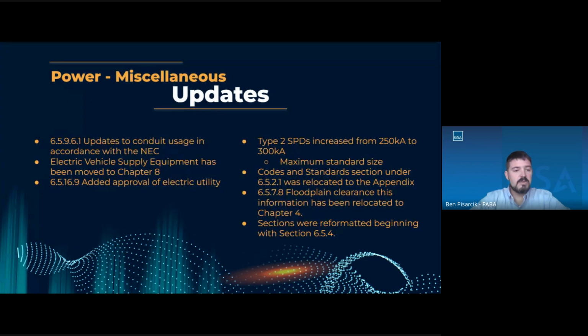Okay, moving on with general updates. So we had a section in P100 that talked about conduit and its usage, and there was some confusion there about, for an example, that all feeders had to be run in IMC and things like that. So we kind of cleaned that up and just harmonized with the code, and anything that is above and beyond code we listed there, such as compression fittings for EMT.